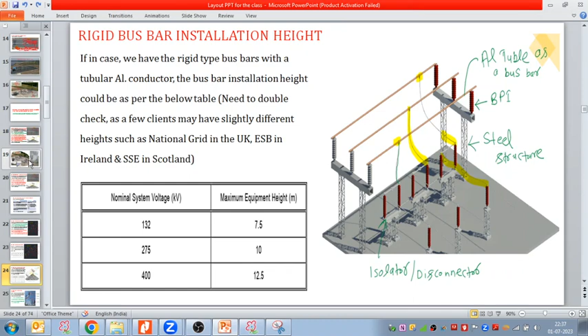Now for the rigid bus bar, let us see again - rigid bus bar installation support. Here we have the aluminum tube conductor, and this equipment is called the post insulator, placed here. This insulator is placed on a common structure where all the R-Y-B three phases will be placed, and this structure is supported with support structures plus insulators, on which we place the conductors.